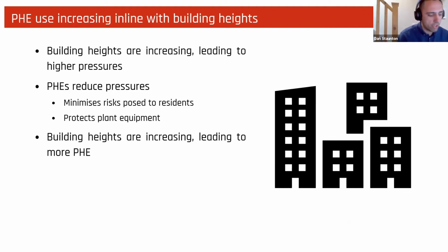So, as an industry, we're seeing an increasing need for plate heat exchangers. Building heights are increasing, leading to higher pressures on networks. Plate heat exchangers reduce those pressures, minimising risks to residents and protecting plant equipment. As building heights have generally increased over the last 5 to 10 years, we're seeing, and continue to see, an increased need for plate heat exchangers. Next slide.